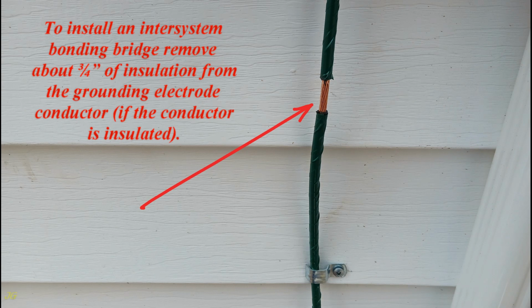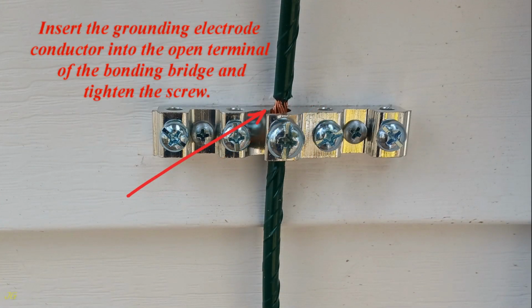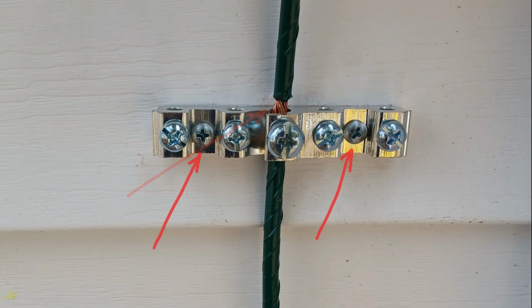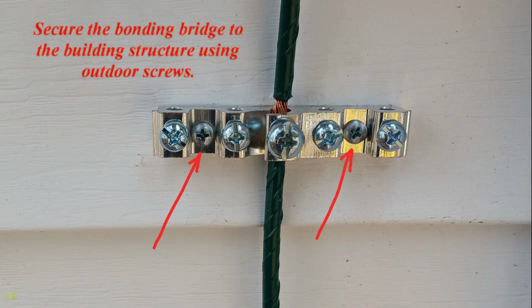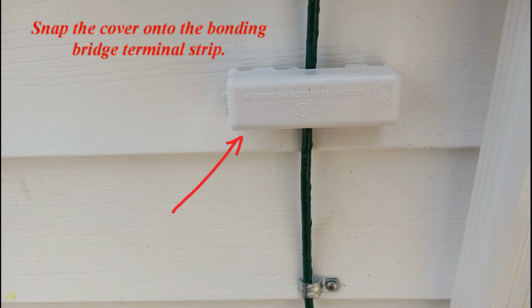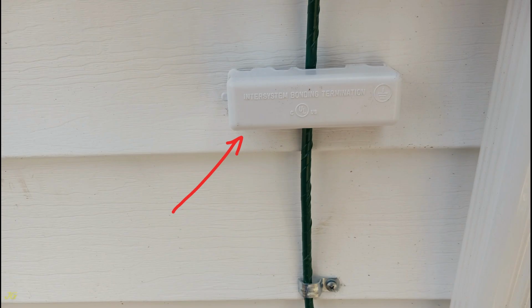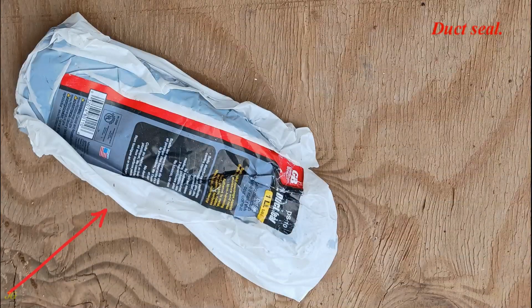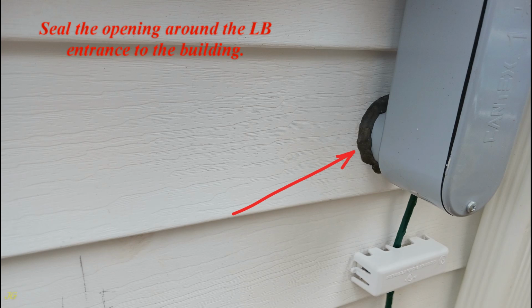To install an inter-system bonding bridge, remove about 3/4 inch of insulation from the grounding electrode conductor, if the conductor is insulated. Insert the grounding electrode conductor into the open terminal of the bonding bridge and tighten the screw. Secure the bonding bridge to the building structure using outdoor screws. Snap the cover onto the bonding bridge terminal strip. Duct seal. Seal the opening around the LB entrance to the building.